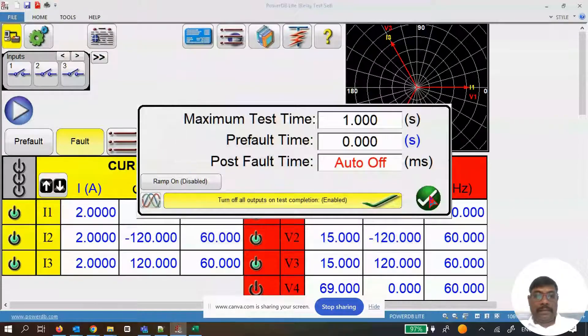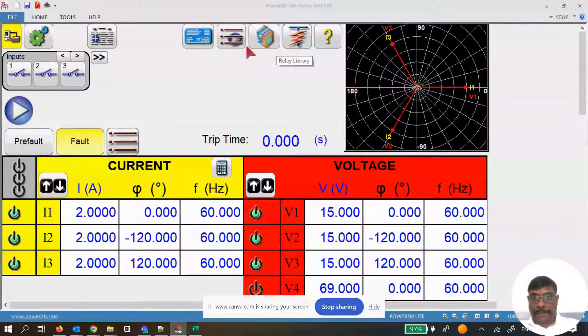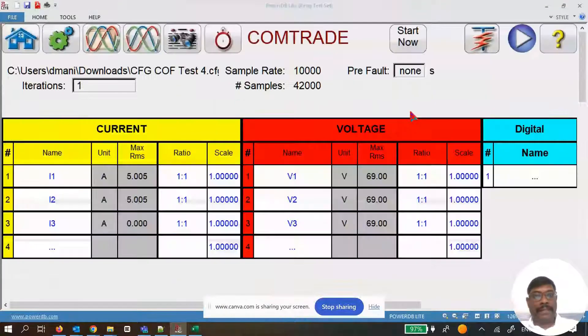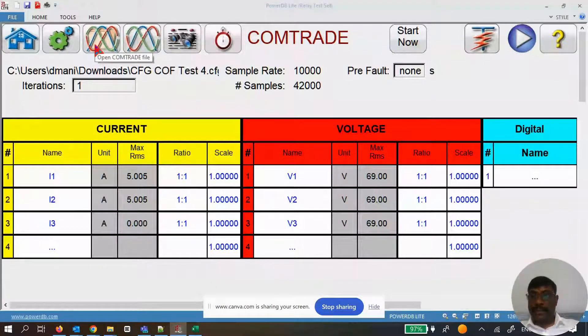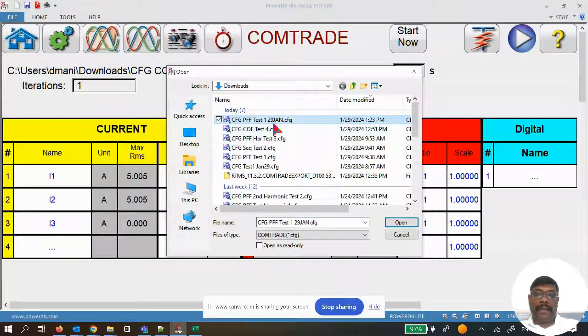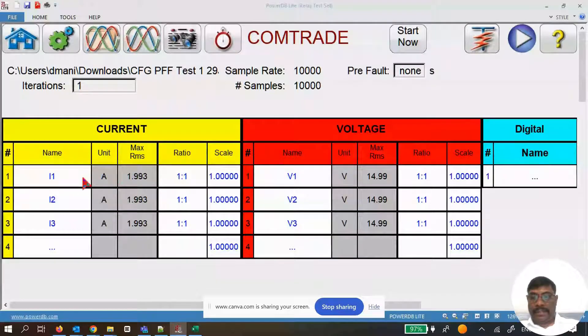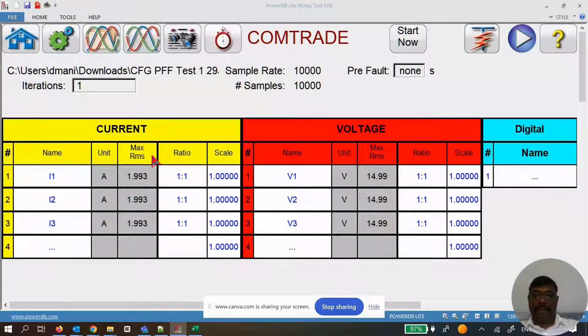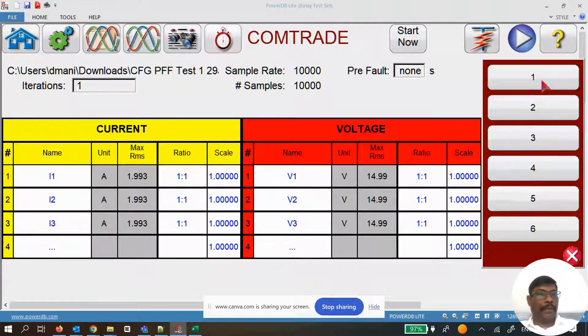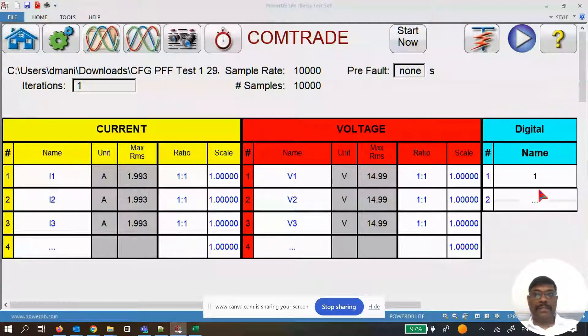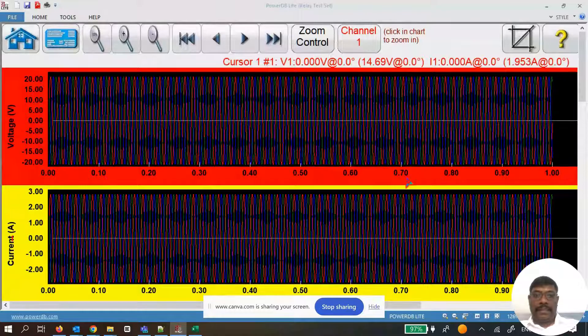Once the test is exported, go to the Tools menu and select the Comtrade screen. Click on Comtrade and use the 'Open Comtrade File' option, then find your file location — in this case, the Downloads folder. Click the file exported from RTMS and click Open. It automatically loads your test files in RMS format. If you want to define binary inputs or outputs, click the digital selection option, and you can switch to waveform view.